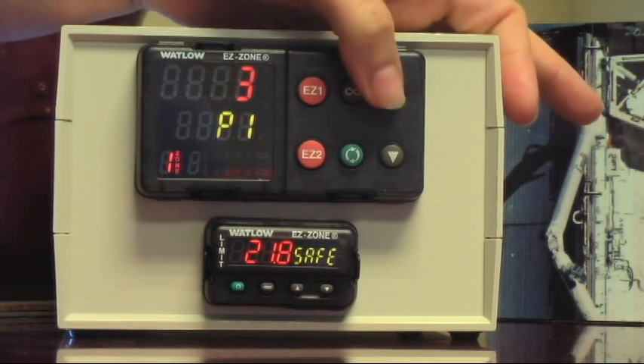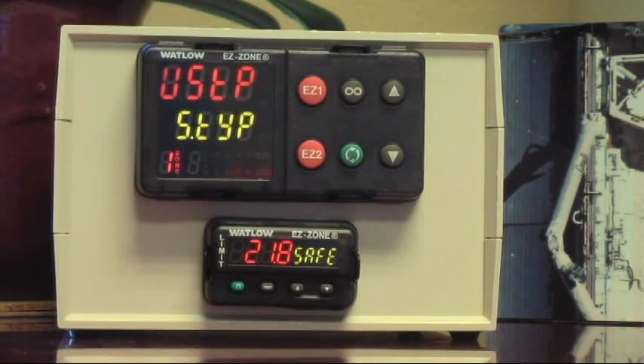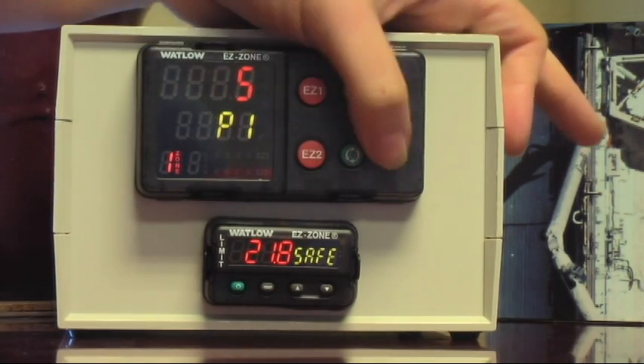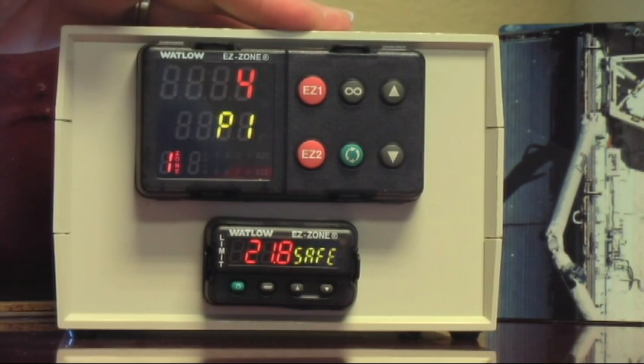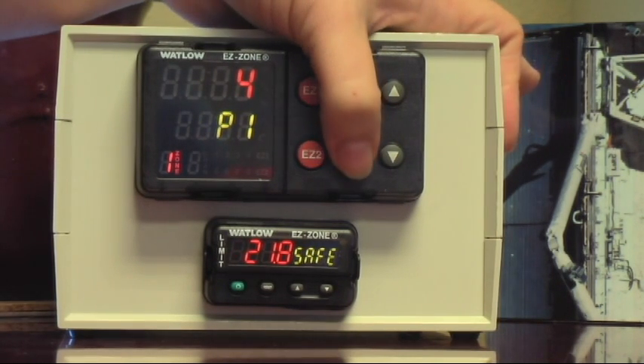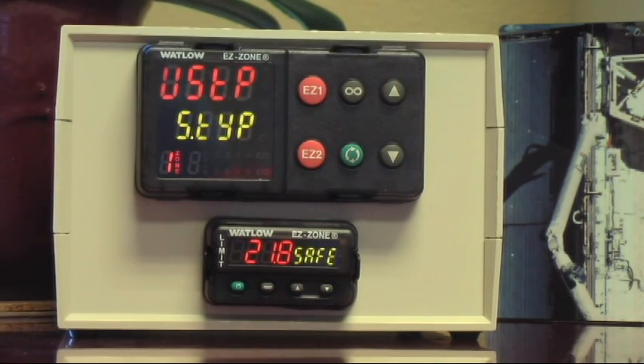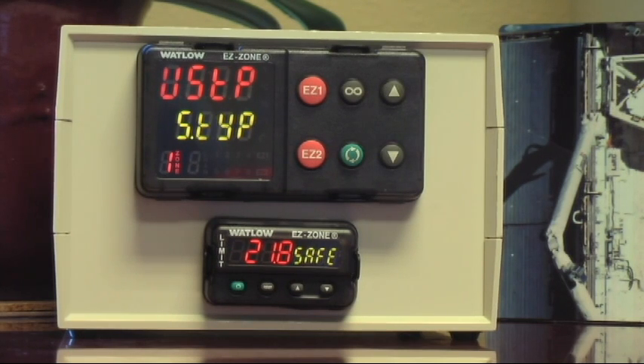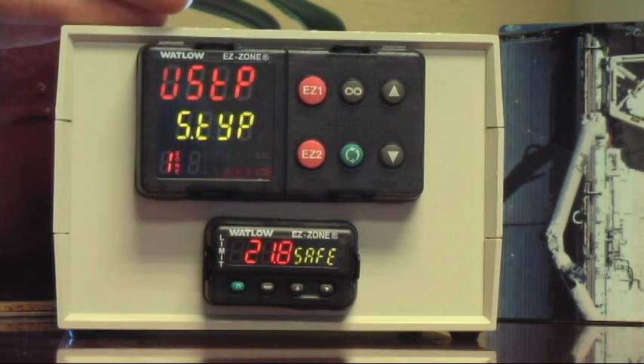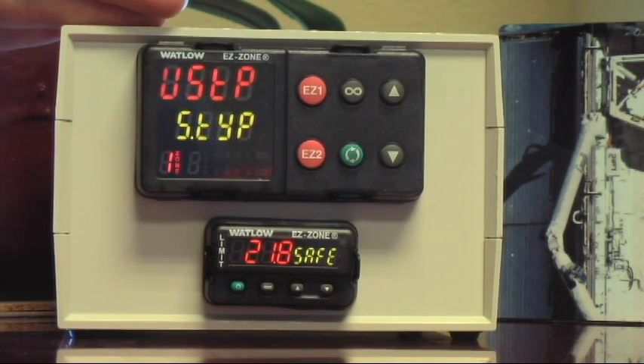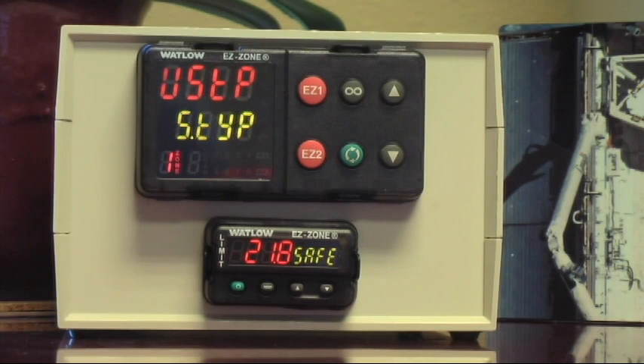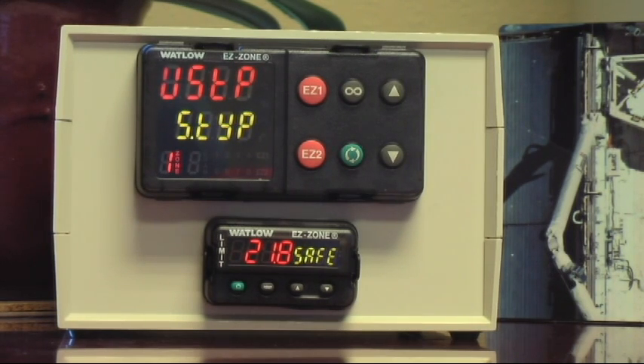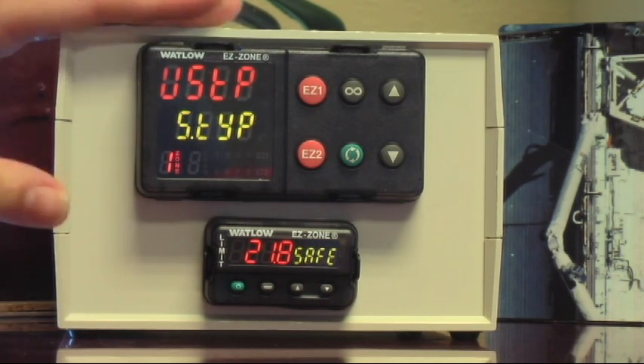Infinity key up to step four. Yeah. I think that went to five accidentally. Uh-oh. Fast fingers. Uh-oh. So right. See how easy it is to fix that? Okay. Green button. Now, step four is a little cascade tech helpful hint. Instead of selecting end here, we're going to just tell the oven to run the temperature all the way down. That way, if you were using the oven previously at a higher temperature, it's not going to revert back to that temperature. It's not going to keep your parts at the hundred degrees, but it's going to run all the way down. So it's really the best way to end here. It's the best way to end the process. Okay. It's just an extra step.